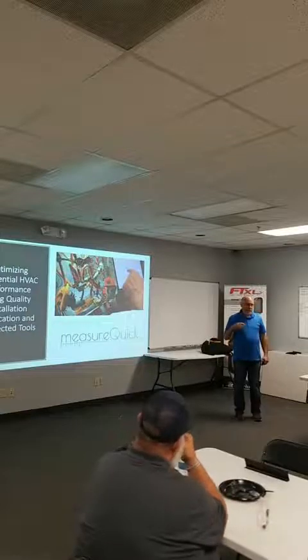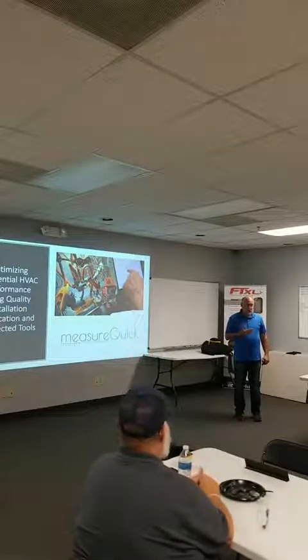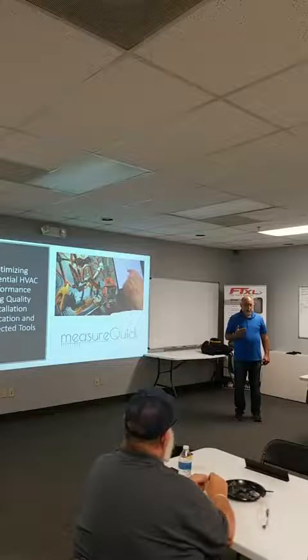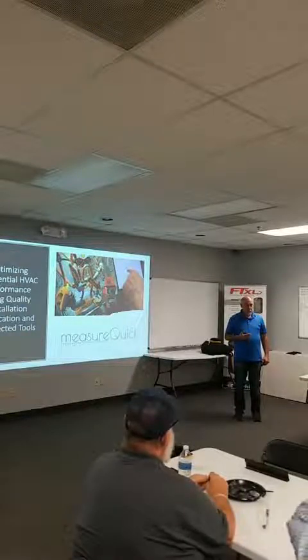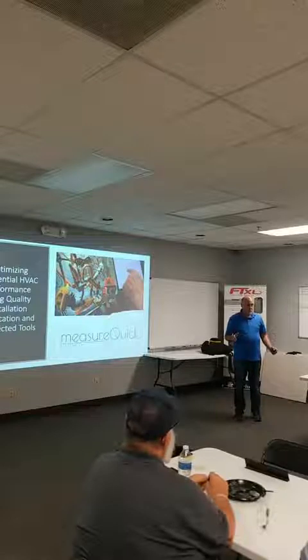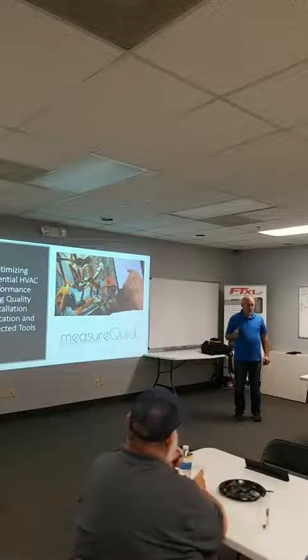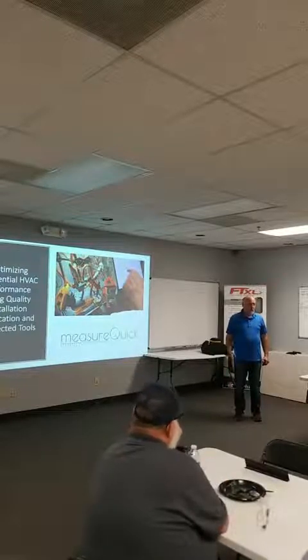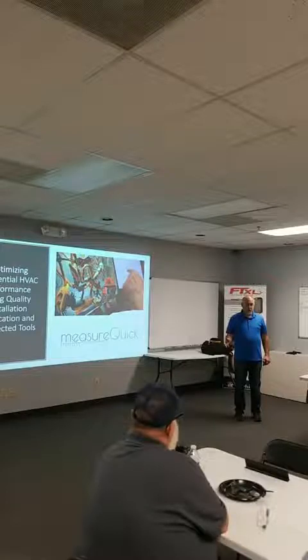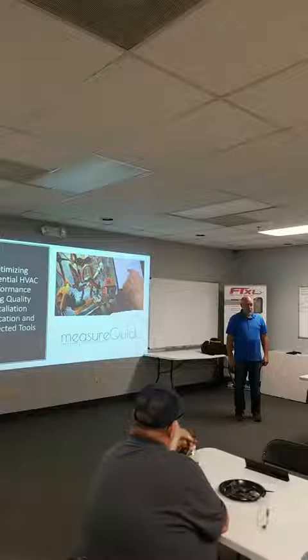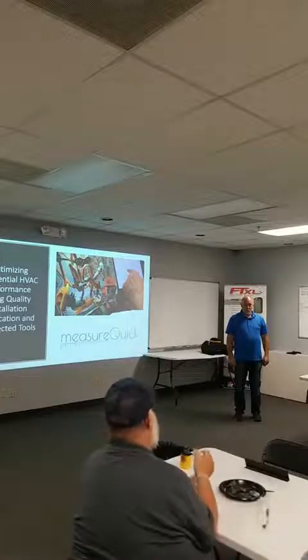And the idea back then was this: I was a trained technician for 15 years. I realized my entire career I'd been making measurements, but most of the time I didn't know why, right? Just to put this in perspective, if I told you it's 81 degrees in your space, with a 67 degree wet bulb, a 92 degree outdoor air temperature, and 400 CFM per ton of airflow, before you hook up your gauges, what should the pressures be? What should the suction line temperature be? What should the liquid line temperature be?